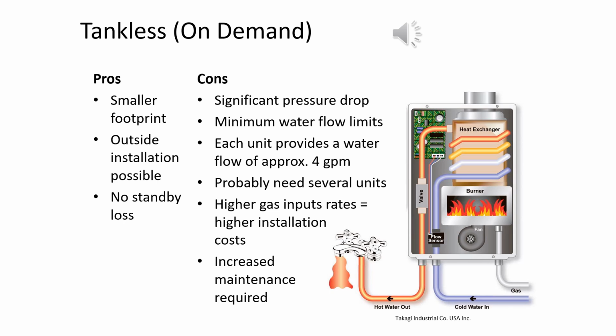The cons are that they have a significant pressure drop. These water heaters have a control system which allows them to limit the outlet flow of hot water so that they can meet their temperature set point. If multiple large points of use are run at the same time, these units will starve the entire hot water system, which can lead to critical hot water failures. There are minimum water flow limits on these as well, so if the demand is small enough, they will just send cold water in the hot water outlet pipe.